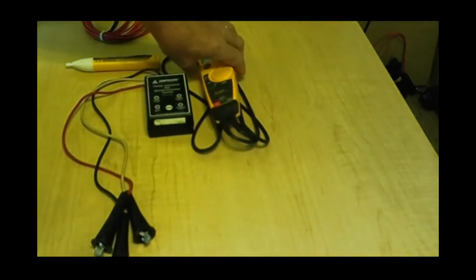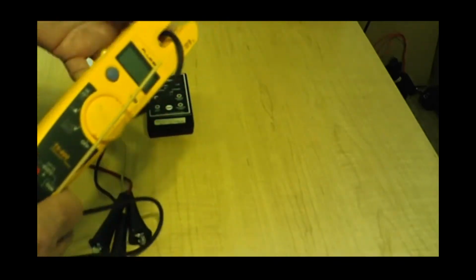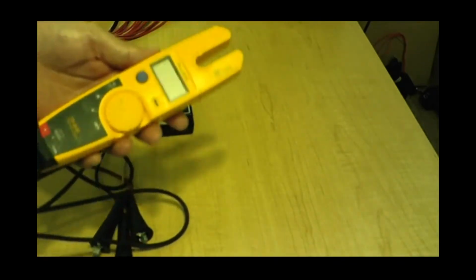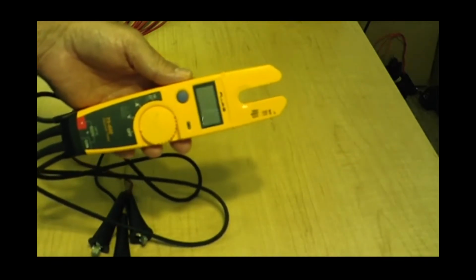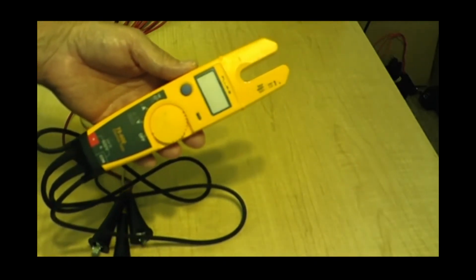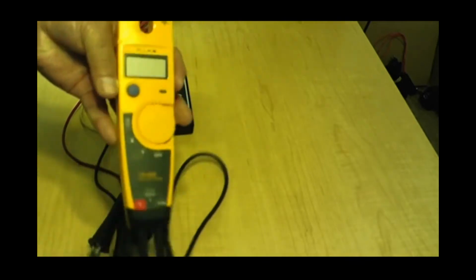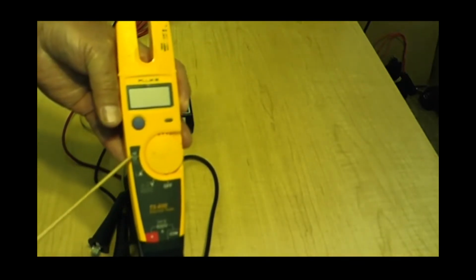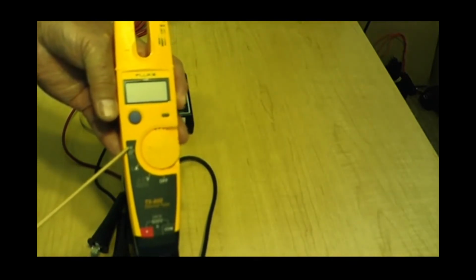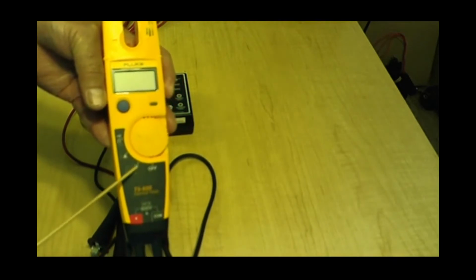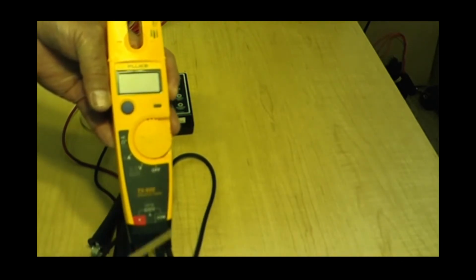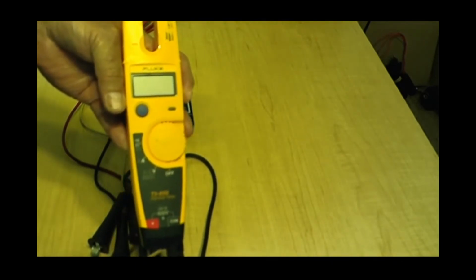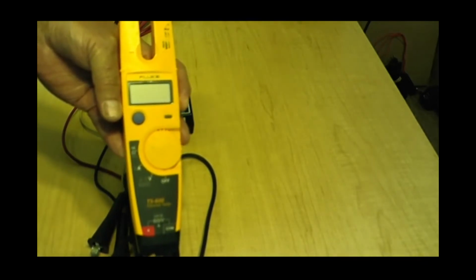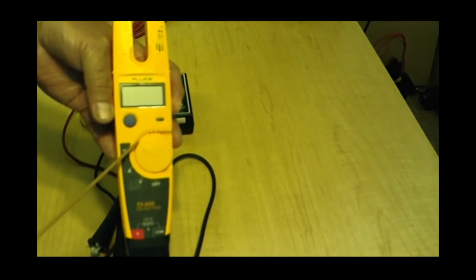Now, a common meter you see in industry is this guy. Most all your electricians and maintenance will be using these things. They're very simple. They're inexpensive. They fit in your pocket. They read ohms, continuity, amps, volts, and they turn off. Test leads are attached. You don't have to worry about testing and changing them. All you got to do is turn it on.